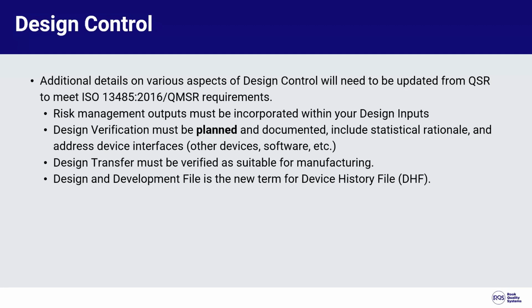Design transfer is covered by the QSR, but the section for design transfer within 13485 also includes a requirement that design transfer is verified as suitable for manufacturing. So under the current QSR, it just states that you need to perform design transfer to change your design into manufacturing specifications. ISO adds a requirement to verify that once it's complete. And we discussed this a couple slides back, but design and development file is the new term for device history file. I don't think anybody's going to beat you over the head if you call it a DHF, but the formal term under ISO and under the new QMSR is going to be design and development file.